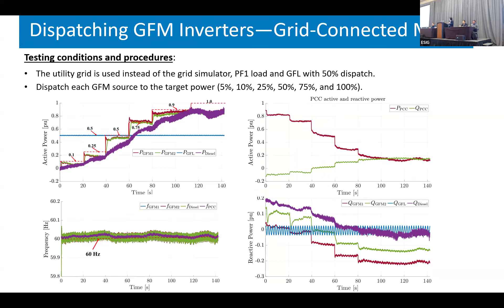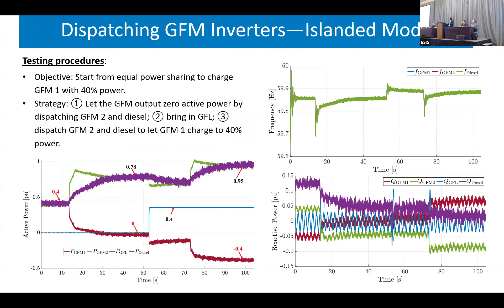The next slide shows that in grid-connected mode, all grid-forming inverters output the target power. For islanding mode, we started from equal power sharing, then had one inverter charge with a certain power. Based on the dispatch rule, this was also achieved. These results validate the dispatchability and interoperability of grid-forming inverters.